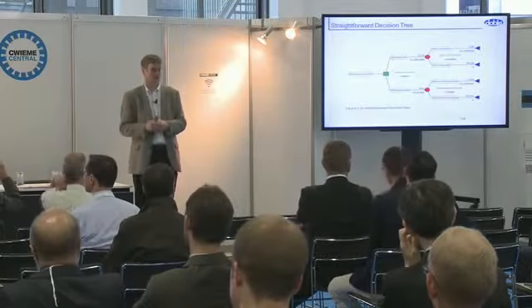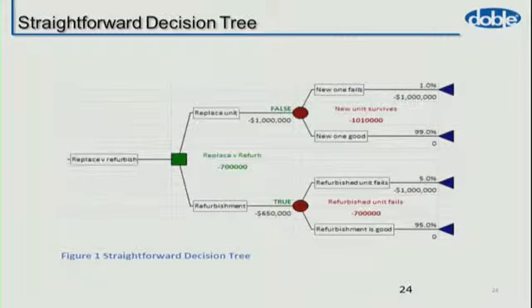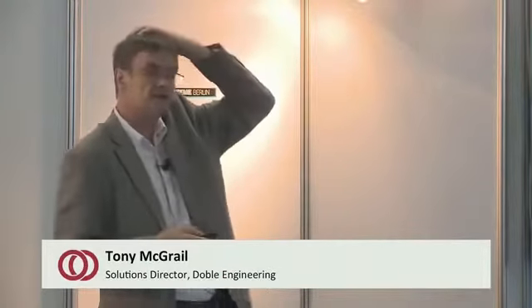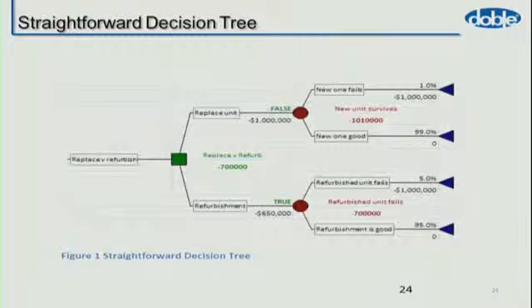So in this case, I'm making a decision. On the left side, I have a transformer, it's been damaged. Do I replace it or do I fix it? Simple decision. In this case, it's false that you should replace it, and it's true that you should refurbish it or fix it. The nice thing about this approach, it's a decision tree, is that you can put prices, you can put dollars against the different outcomes, and you can put probabilities. So we've identified that the chance of a new one failing is 1% at $1 million, and the chance of a refurbished unit failing is 5%. You can then work out the expected monetary value of your decision, and you should refurbish.